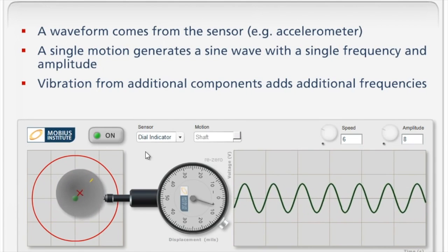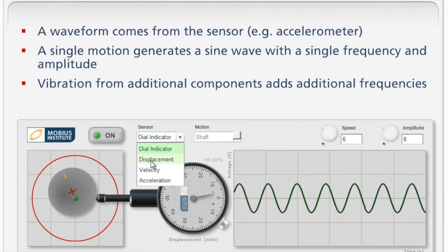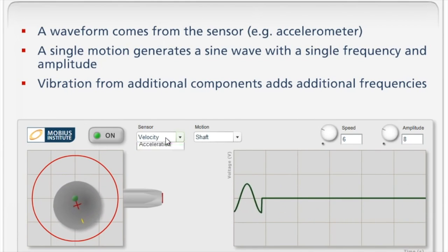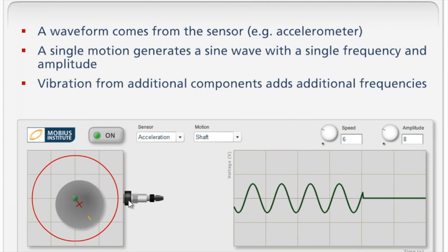This isn't the way we normally measure vibration in certain machines. We can use these non-contact eddy current probes, also known as proximity probes, which literally measure the distance between the tip and the shaft. We used to use velocity probes a lot, but now it's more common to use accelerometers. It sits on the bearing housing and senses how it is moving in response to all the things going on inside the machine.